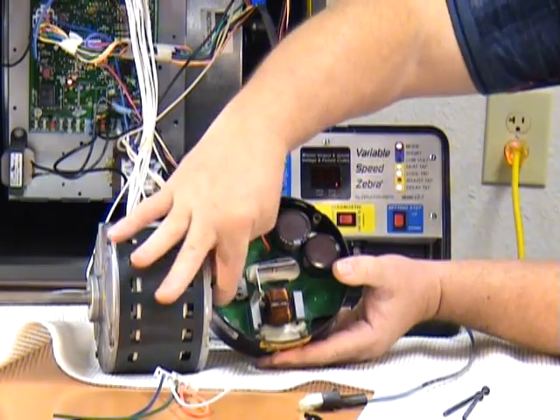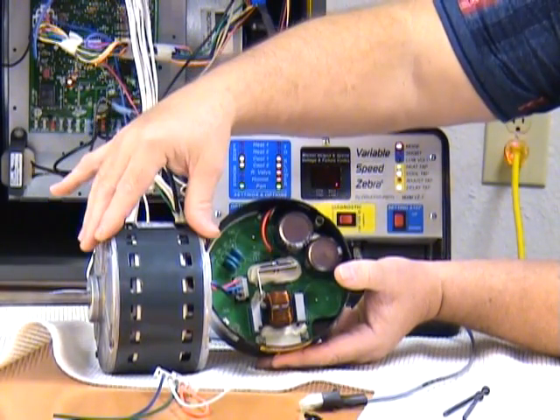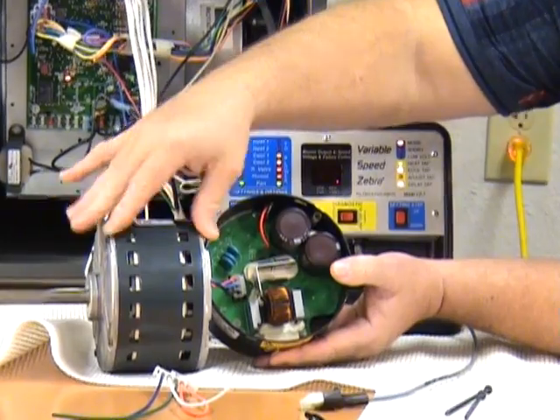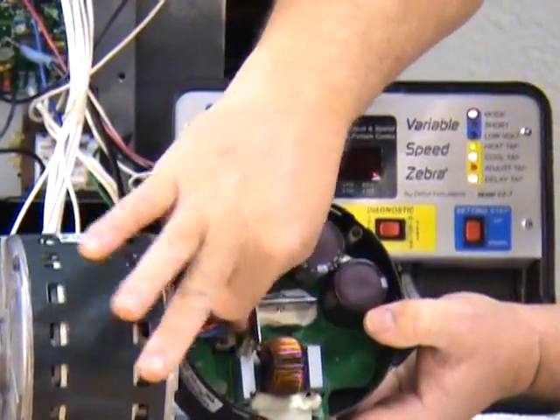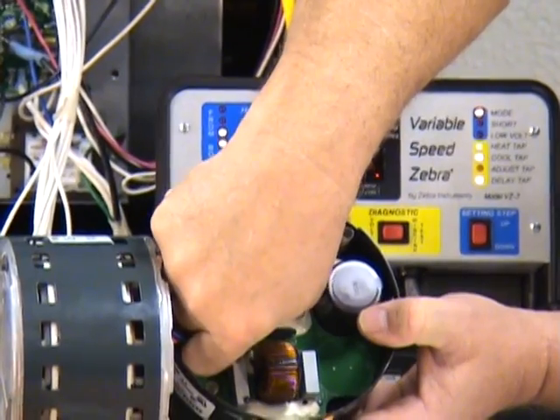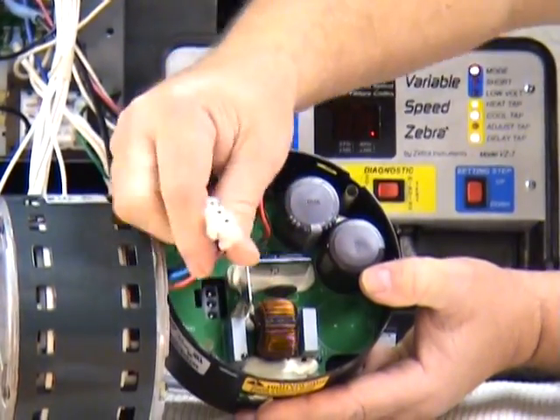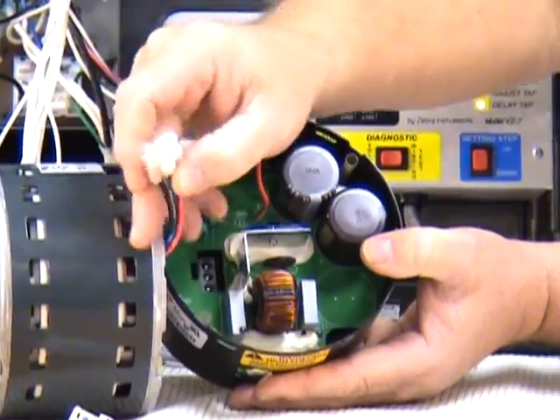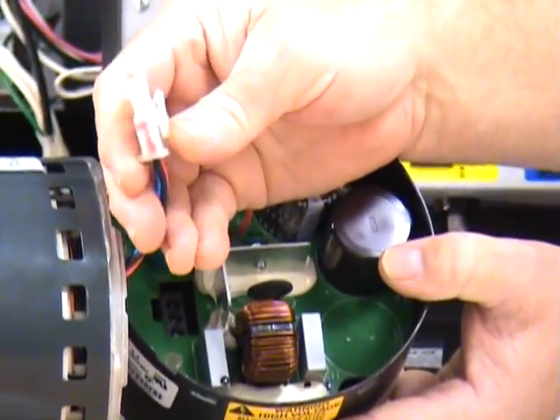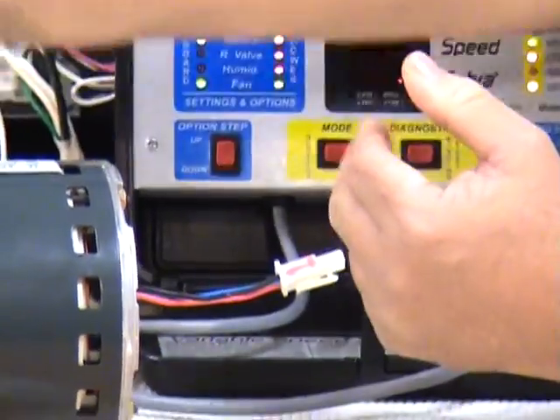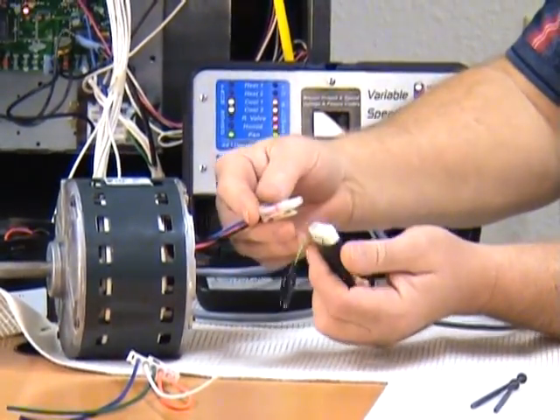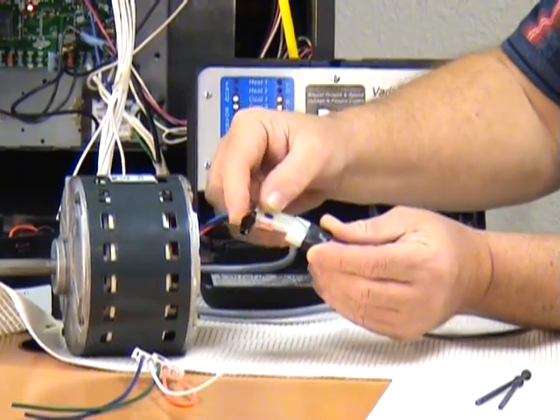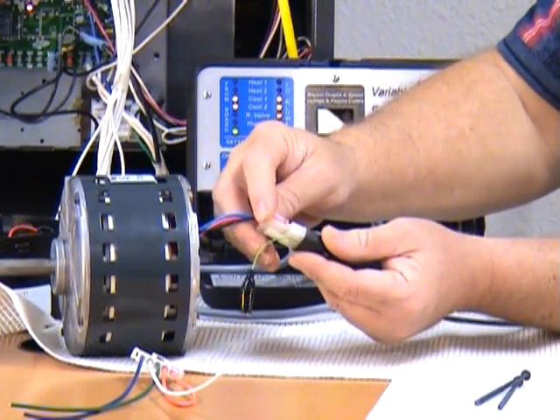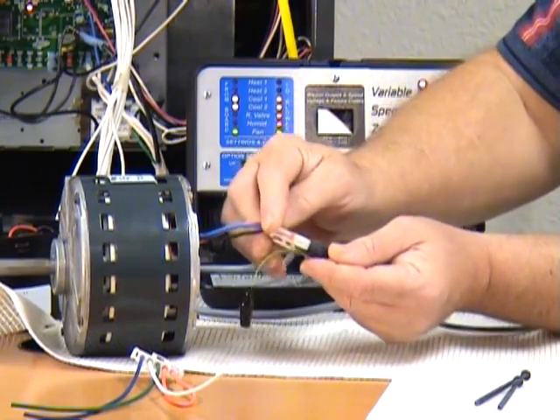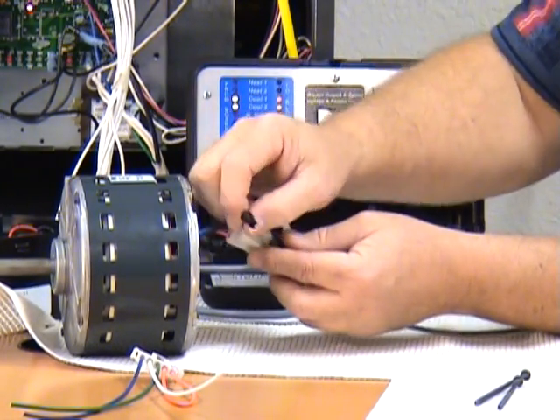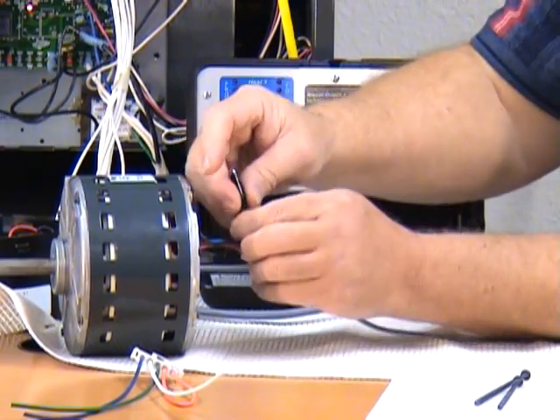Inside the motor, there's only a 3-wire harness going between the winding section and the electronics module. There's a little connector on the end of that harness, and it has a squeeze tab, which is a little difficult to get to, but you must push the squeeze tab in before the connector will release. Can you see the squeeze tab there? Okay. That squeeze tab is what connects up to this 3-pin harness that we spoke of earlier. It'll only go in there one way. And it goes in a lot better than those 16-pin connectors do. A lot easier, I'm sorry.